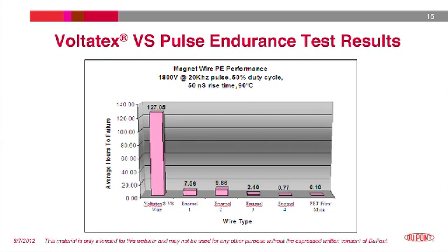In one specific case, an engineer was designing a low voltage motor for an application where the threat was an inverter which creates dV/dt, which accelerates degradation of the wire enamel. We evaluated this threat using a 20 kilohertz pulse with a 50 nanosecond rise time. We conducted testing on a variety of corona-resistant magnet wire insulation solutions, and the best material was the Voltatex VS wire enamel. Voltatex VS provides corona protection by using nanotechnology at a polymer level, rather than through the use of fillers. We additionally evaluated these insulation materials under AC sinusoidal voltages above the corona inception level, and the Voltatex VS again outperformed other wire insulation under the conditions of test.